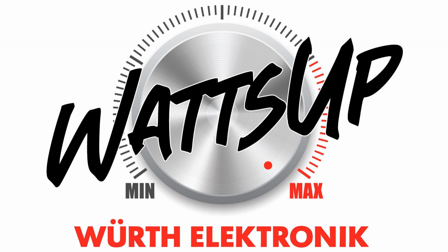So as we saw before, the X and Y define the position of the connection in the mains power lines. Then there is the number that represents the surge voltage capabilities. So for example, X2 caps are certified to be able to withstand a defined pulse of 2.5 kilovolt. And then the self-healing process will fill the gap and the capacitor will keep working with some capacitance drop.